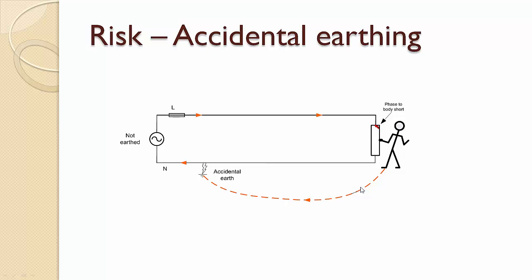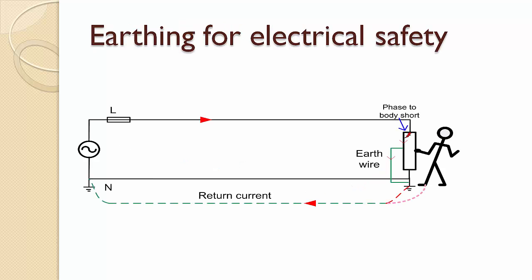So you can see that the global conductor nature of the earth poses a safety threat in this case. You may also appreciate that if the same conductor as the faulted one is earthed accidentally, the person handling the equipment will not feel a shock because now there is no complete path from line to neutral. To provide this bypass to earth, it is necessary to earth one of the supply terminals to complete the path of the fault current. For this reason, it is mandatory for modern electrical supplies to be earthed, except for special cases.